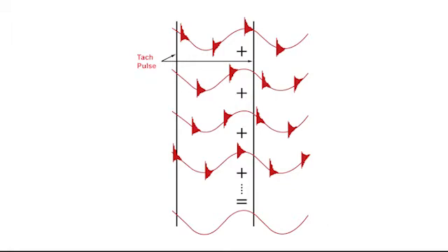But data collected from other shafts or where there are bearing problems will be inconsistent. If we average all the data, the synchronous data will be very dominant, and the non-synchronous data will be averaged out.